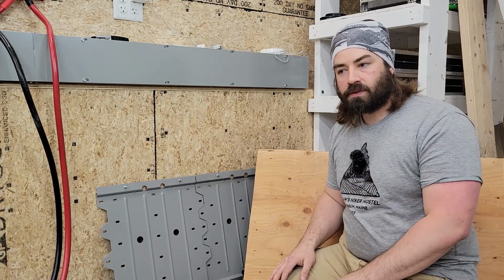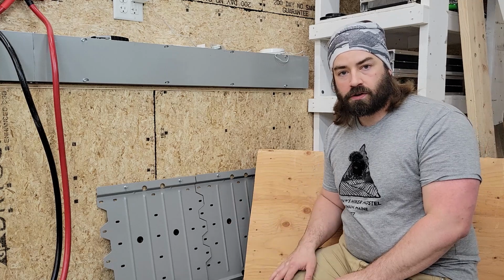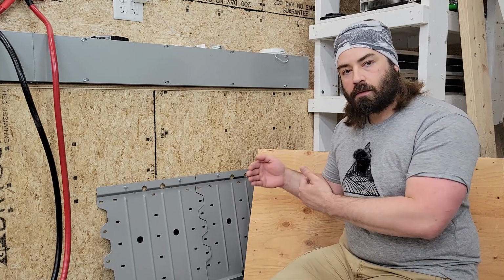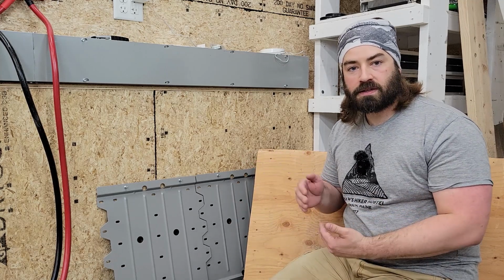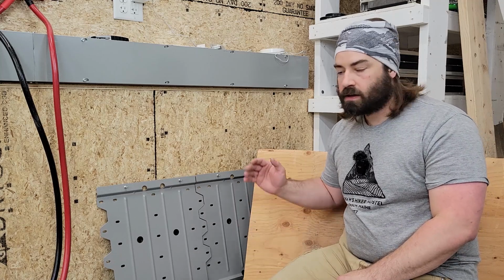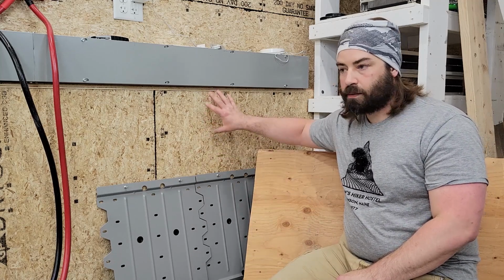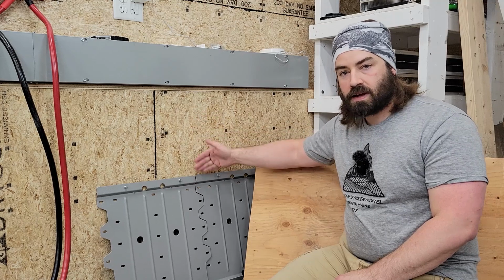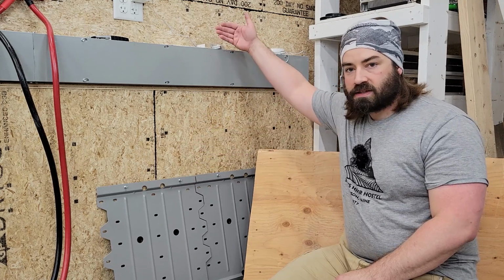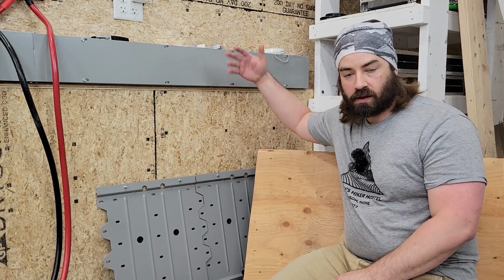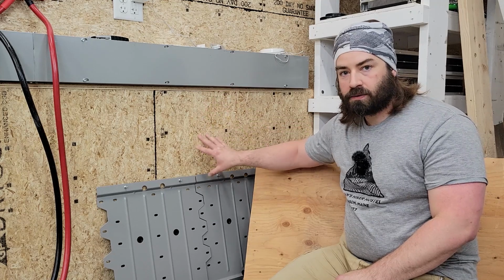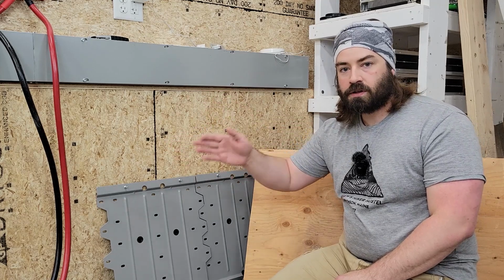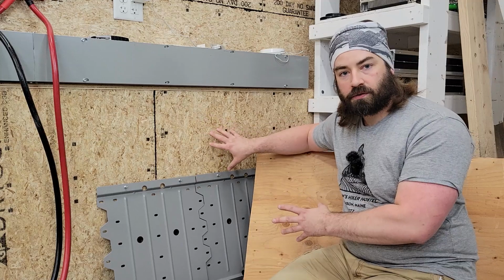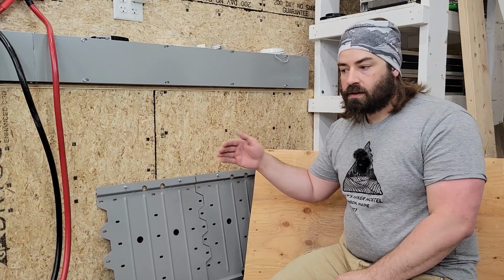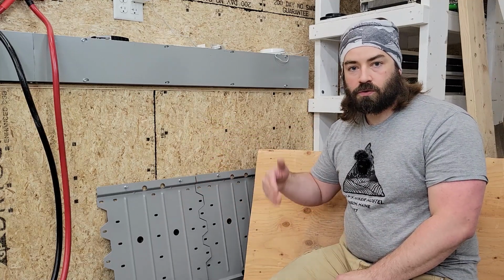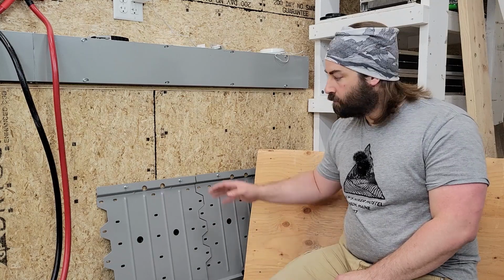If you're going to mount these underneath something like your inverters, they can't stick out more than 6 inches past the front face of the inverters or circuit breaker box. In my case, I have a step because of the concrete stem wall behind here, which then steps back to the stud wall above. So I can't mount these directly underneath my inverters, that's why I'm putting them off to the side. You also need to maintain clearance underneath the PDP to access the circuit breakers.